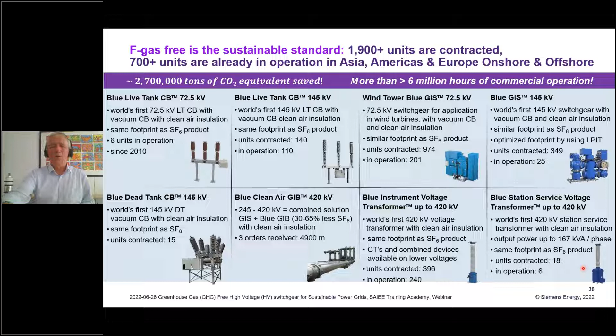Just to give an overview of some products, this is the 145 kV live tank circuit breaker. From the outside, you don't see a difference to the SF6 technology. In here is the vacuum interrupter, up here, and it's surrounded by clean air. So from the outside, it's hard to see. You see it a bit: the diameter on the upper insulator is a bit bigger than on the lower one because the vacuum interrupter is in there, but that's the only way to see it.